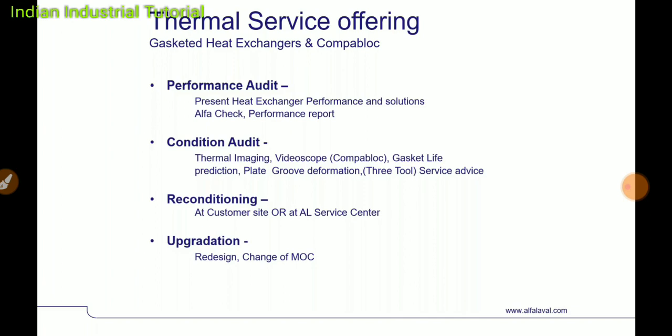Similarly, condition audit is also offered by Alfa Laval. We have a thermal imaging camera, and we show the thermal camera reports in the next slide. The thermal camera is put on the heat exchanger, and during working we can see the clogging or malfunctioning of the heat exchanger without opening it, in an on condition.